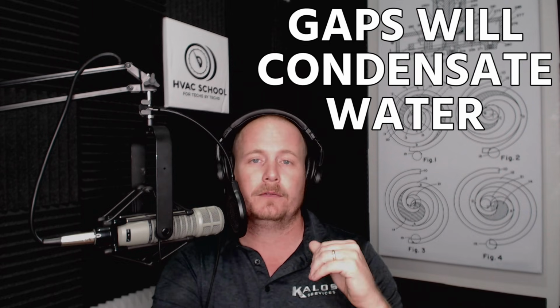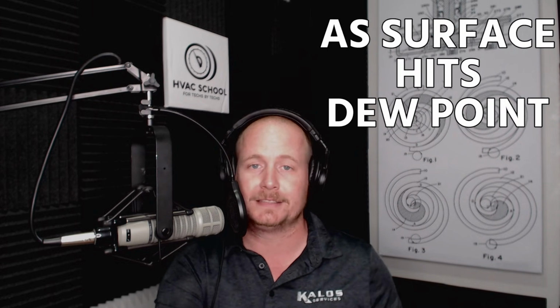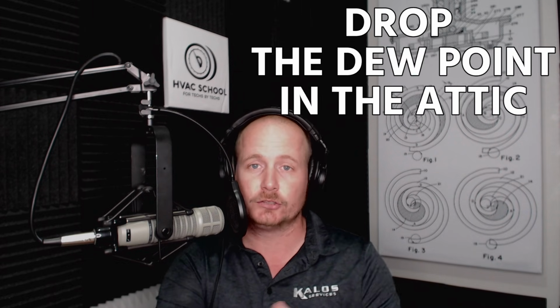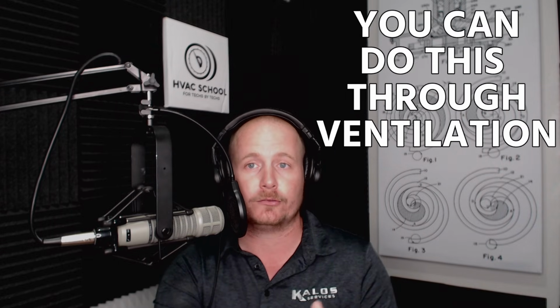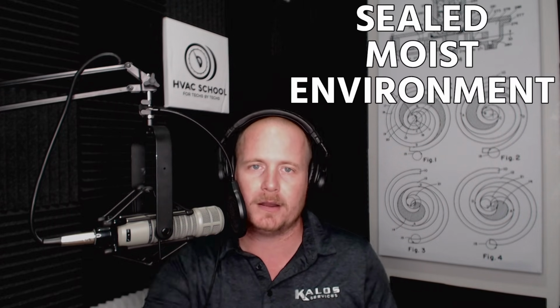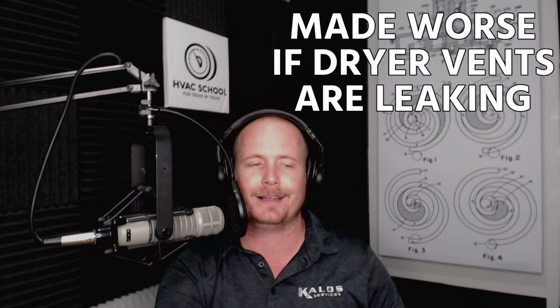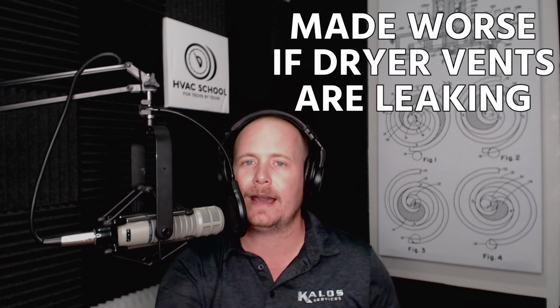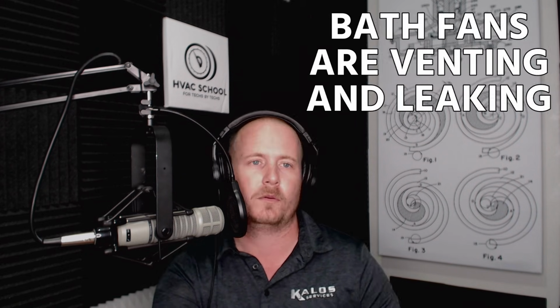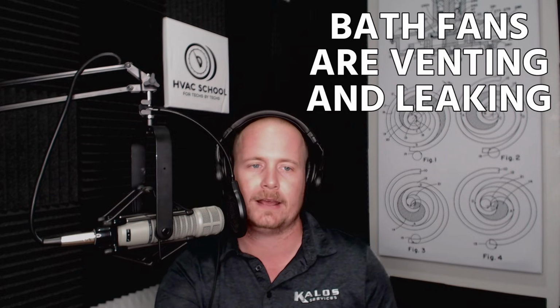Insulating properly is super important, and so if you have gaps in insulation, obviously those will condensate water as that surface hits dew point. A better way to deal with this is to drop the dew point in the attic, and you can do this through ventilation in some cases. It's worse if you have a sealed, moist environment, and this is especially made worse if things like dryer vents are leaking in the attic or venting into the attic, heaven forbid, or bath fans are venting or leaking into the attic, or kitchen exhaust.